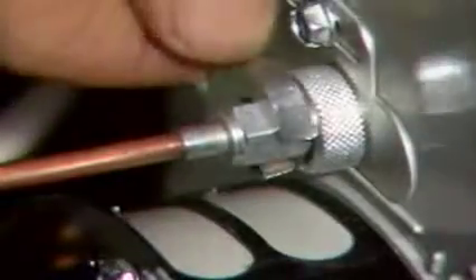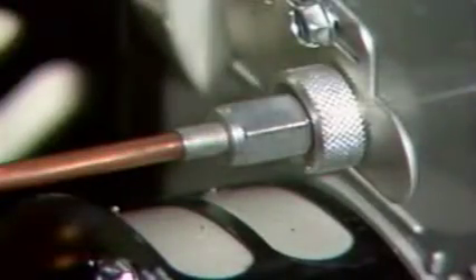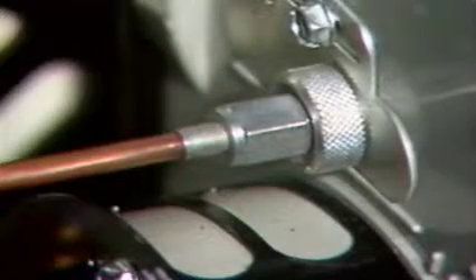To check burner operation, reconnect the nozzle line fitting in preparation for a fire test. Reset the primary control if necessary. Fire the burner, paying close attention to the light-off characteristics. Is the ignition fast and smooth? Are there any delays or puffbacks? Use a flame mirror if possible to observe the flame. Is the flame base stable? Close to the combustion head? Centered? Uniform in shape? And relatively quiet?